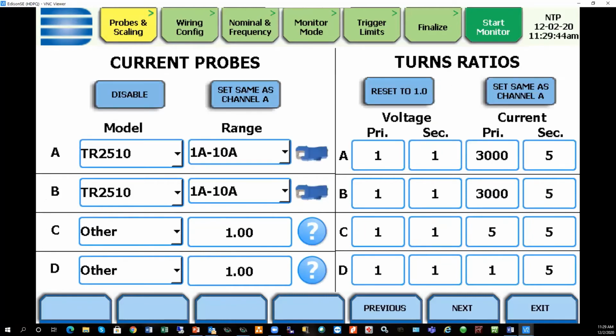This is where you're telling the instrument about the current probes that you're using. Of course, there are a number of different current probes. As you can see here, it's a little bit slow, but it'll eventually load. So you can see the various different current probes that you can use. If you're using turns ratio, that's important if you're involved in medium and high voltage applications, where obviously you can't bring those values directly to the instrument. In those applications, you usually piggyback off existing PTs.